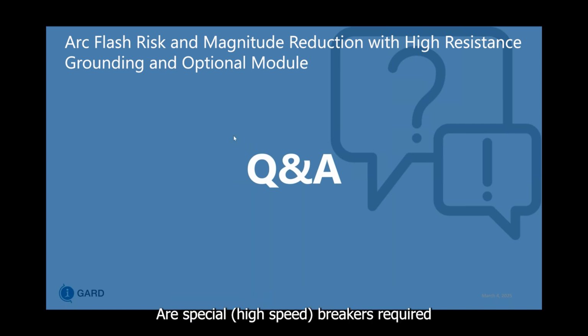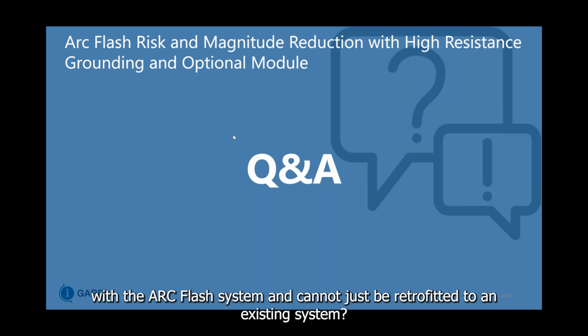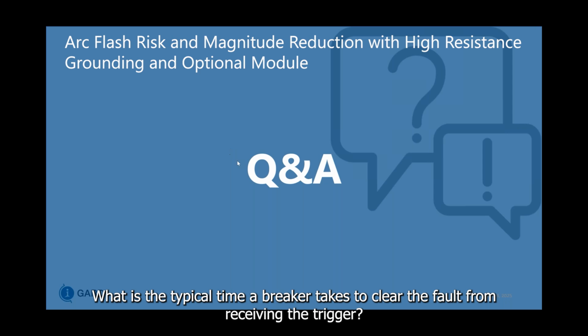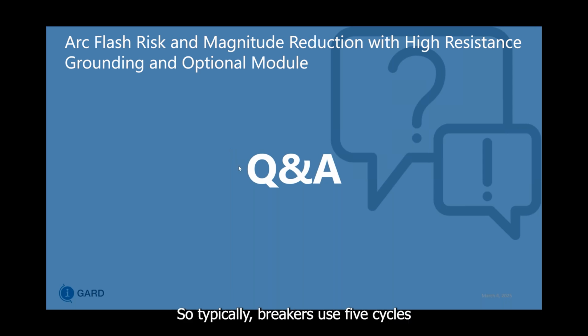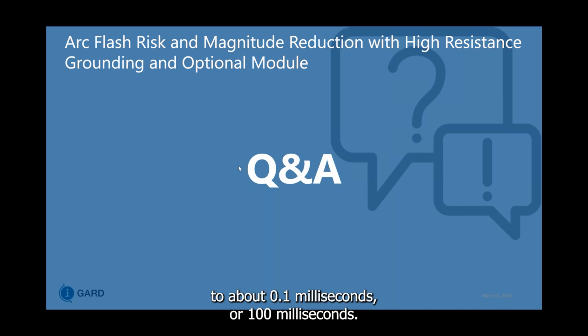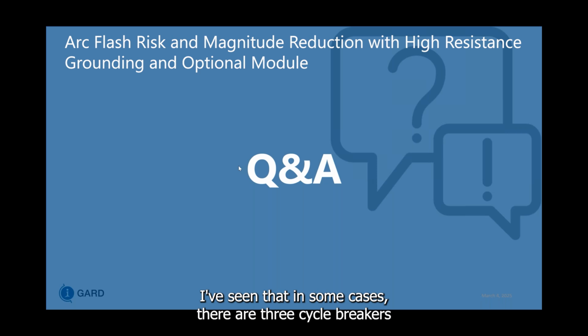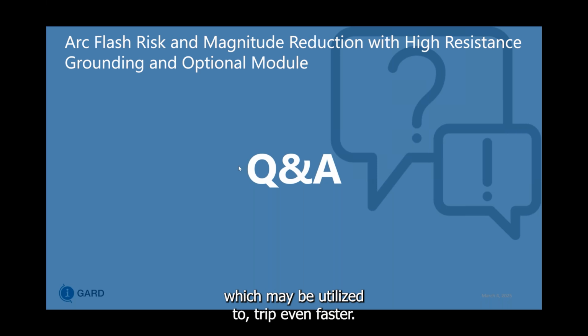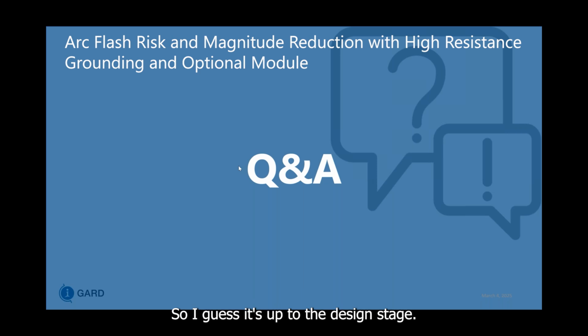Are special high-speed breakers required with the arc flash system, or can it just be retrofitted to an existing system? What is the typical time a breaker takes to clear the fault from receiving the trigger? Typically breakers use 5 cycles before they can trip, but the command from our relay sends it within 10 milliseconds. So 5 cycles equates to about 100 milliseconds. I've seen that in some cases there are 3 cycle breakers, which may be utilized to trip even faster. So I guess it's up to the design stage.